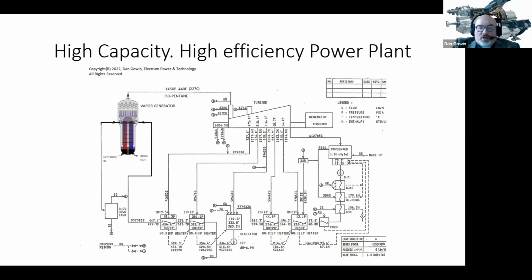Based on that type of energy source, using 18-inch drill pipe, with water going up and back down at probably about 55,000 gallons per hour, I'm able to maintain a load between 20 and 110 megawatts, and it's dialable on an hourly basis. Depending what the power grid in Hawaii needs, this is a nice, sustainable, reliable base load.